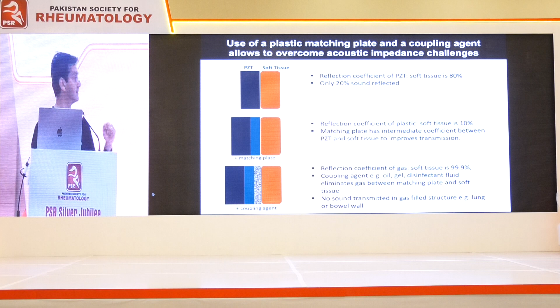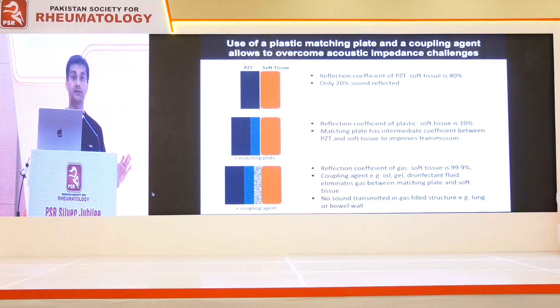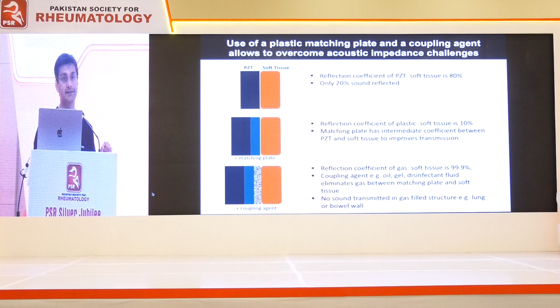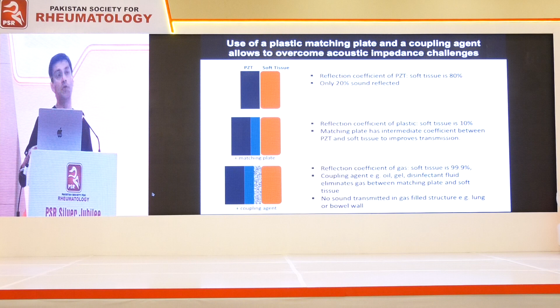And that's actually all the gel does. And actually you don't need to use gel, you can use water, you can use saliva. In some cases, if you're draining an abscess, you can even use the abscess fluid. I mean, you shouldn't, but the point being is that the only purpose that the gel serves is to eliminate the gas between the plastic plate and the skin. And that's why it's important to have that, because by doing so, it allows a greater degree of sound penetration or sound transmission. That's it, that's the main physics bit. There will be one bit afterwards, but if you can grab what I just explained to you, that will allow you to manipulate your machine.